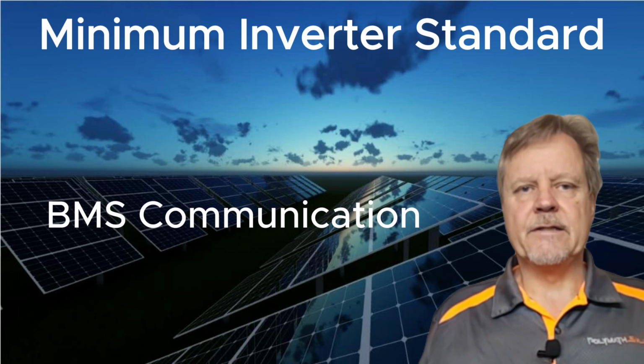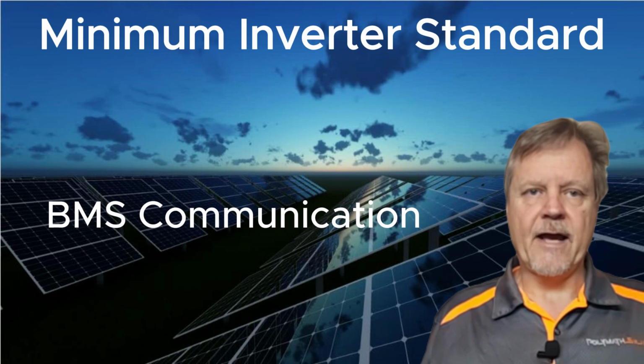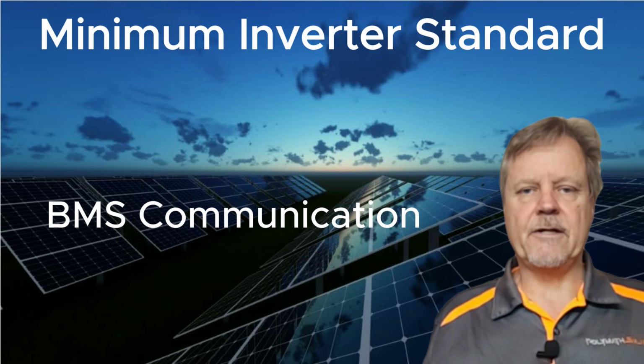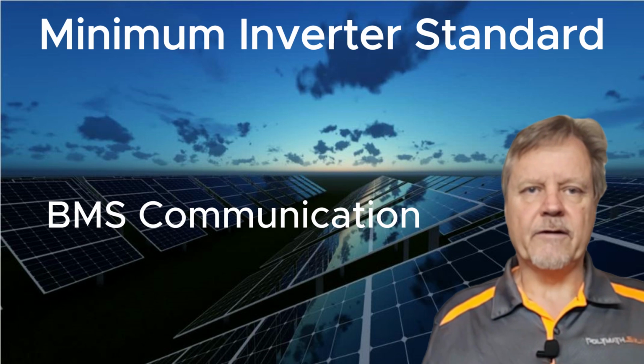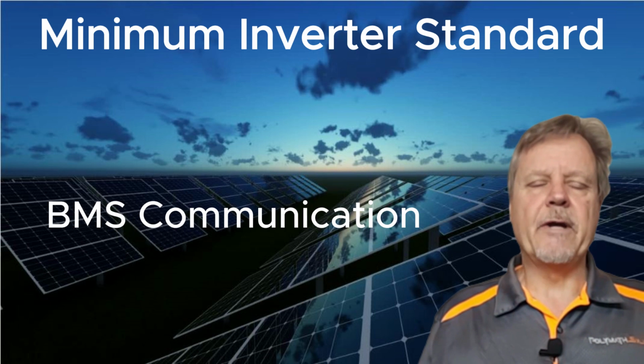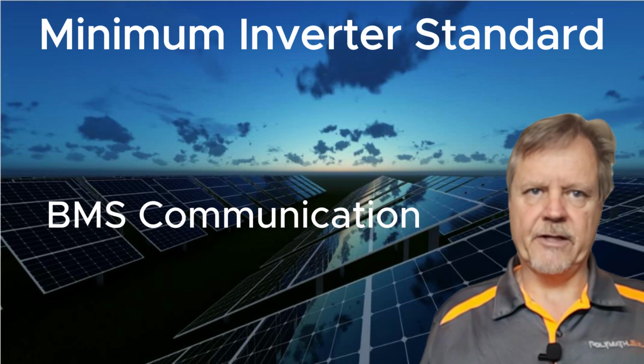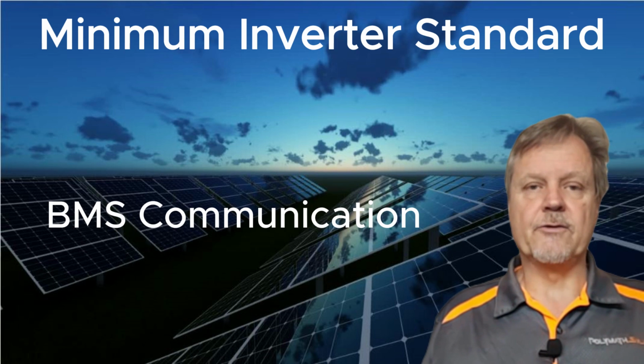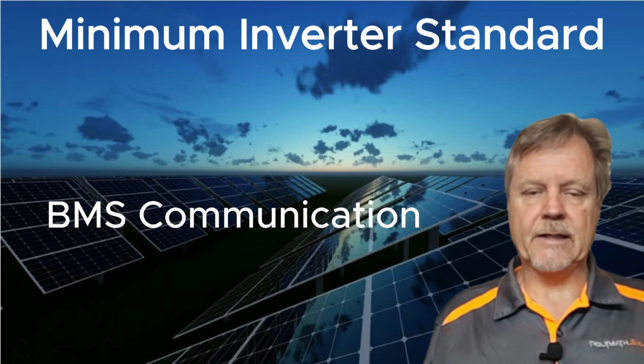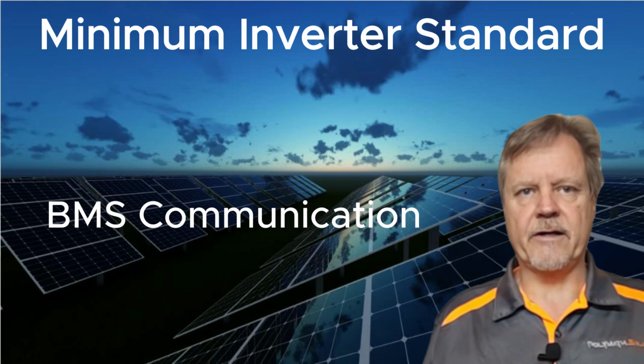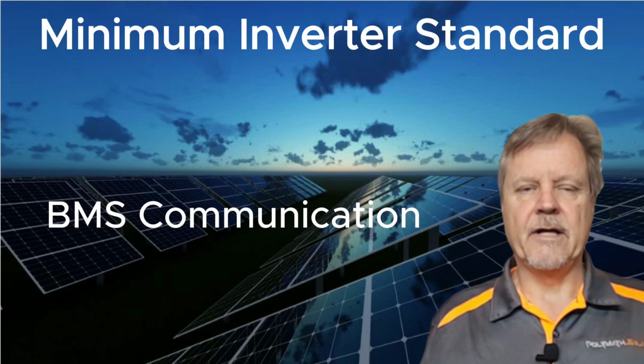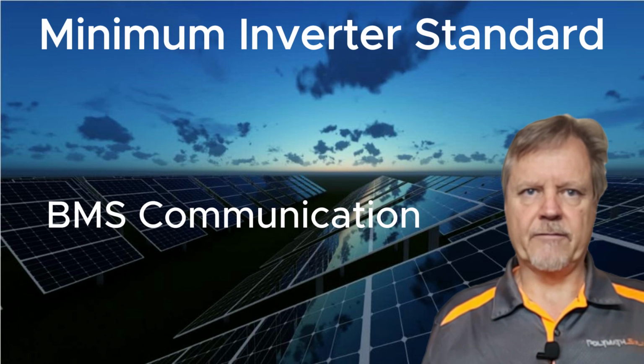When something isn't happening the way it should, the BMS communicates that to the inverter. If you're logging into your inverter's monitoring platform, you'll see reports from the battery, useful for preventative maintenance, showing if the battery is being misused or abused, so you can adjust the inverter's programming.